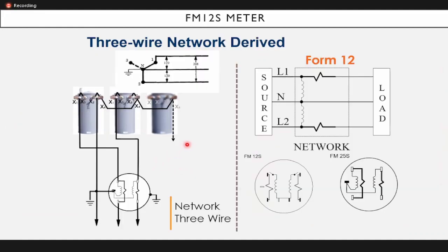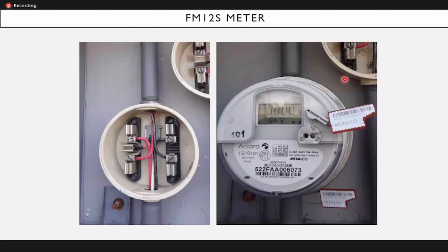This is a three-wire derived network. And for a three-wire derived network, what we use for the meter is Form 12. Usually, the three-wire derived source is for multi-metering centers. Since the source came from three-phase, the single-phase load will use Form 12S. This is an example of multi-metering installations with line-side gutter installed in between two meter centers. So, meron pong meter center sa taas, meron meter center sa baba, line-side gutter po sa gitna. So, this is a typical installation.